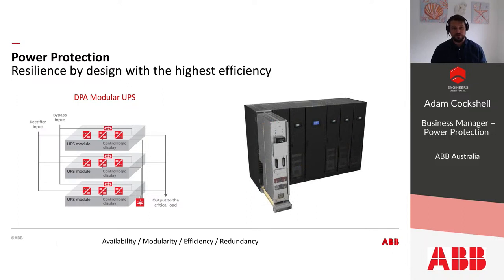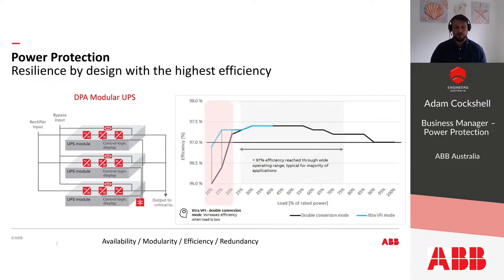With a module efficiency of up to 97.6% whilst in double conversion mode, we not only have an easy to maintain design, but an extremely efficient one. To add to the efficiency across the loading of the UPS, we can also enable what we here at ABB refer to as Xtra VFI to provide higher efficiency at low loads, showing here that at loads as low as 15%, we can achieve 97% or greater.